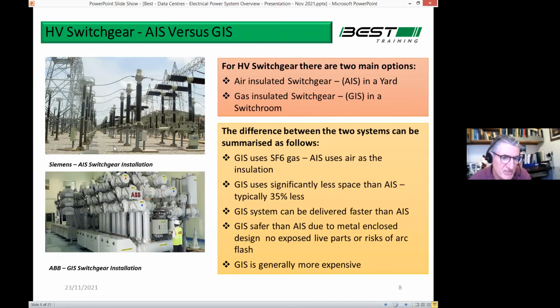You can see the top image here. That's what we call air insulated switchgear, and it's called that because literally the conductors are insulated from one another by air. They're typically separated, phase 1 from phase 2 from phase 3, in air, typically maybe 1.5 to 2 meters apart, as you see there.